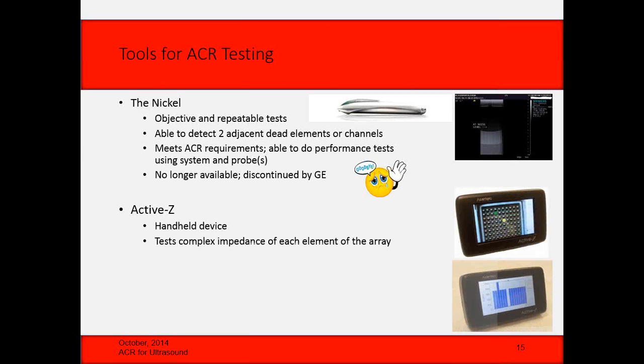put your test lead on this pin. And so you put it there, and it tests the complex impedance from that pin all the way out to the element of the probe and back. And if it's good, it turns green, and then it turns the next pin you're supposed to probe yellow. If it fails, it turns red. And then the bottom picture there is what the test result looks like.